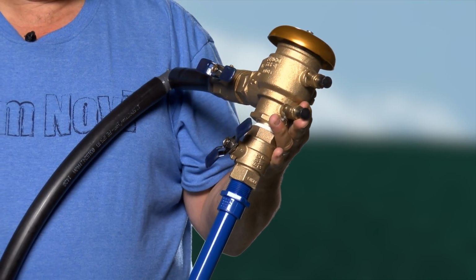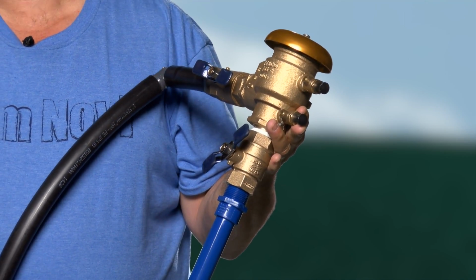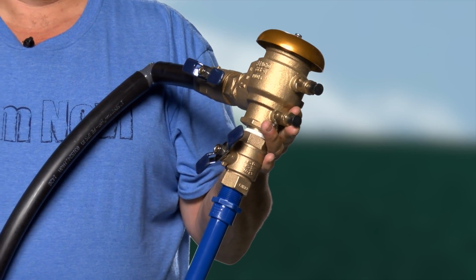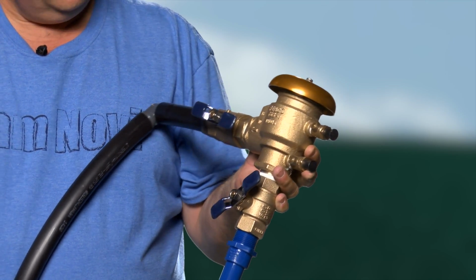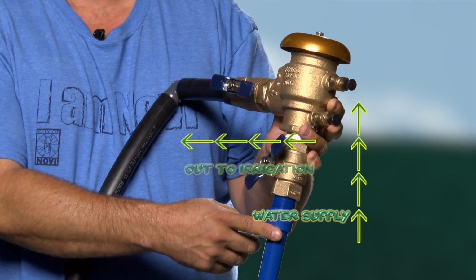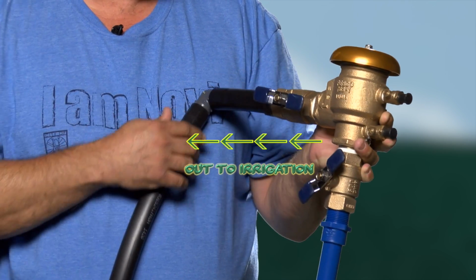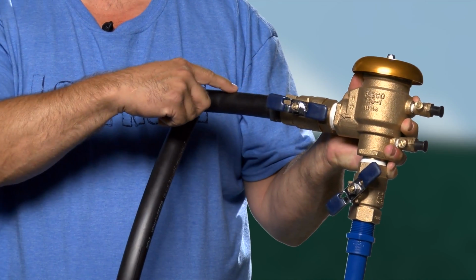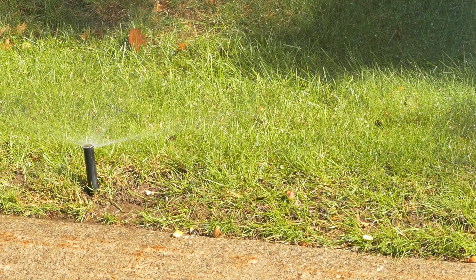Now, one of the more typical or common types of devices, or I should say assemblies, that you're going to see on the side of your house. This is a pressure vacuum breaker. And this is something that is primarily used on your lawn irrigation system in your house. And you've got your water supply coming in that you're feeding it, and you're going up through the device, and you're coming back and you're connecting to your lawn irrigation piping system. And then you've got the various different heads, pop-ups, misters, so on and so forth.